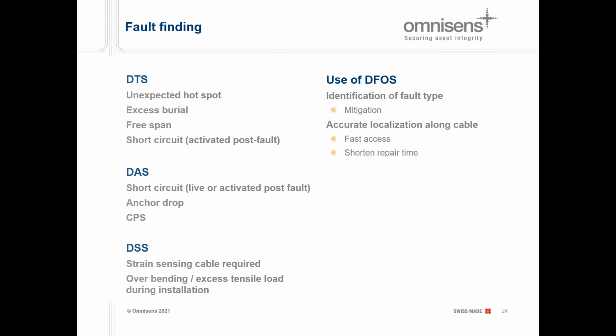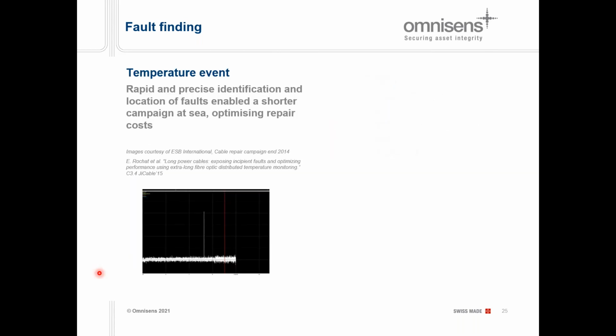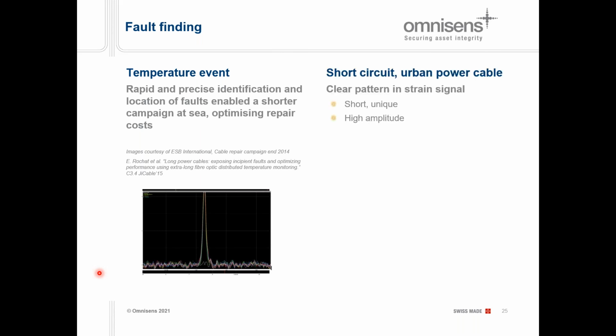A first example we published a couple of years ago relates to a fault found using DTS on a cable where the company had been looking for the fault for months. Eventually they decided to give DTS a go. Fortunately there was a fiber there, and when they activated the fault, there was a clear hotspot, easily localized. With fine-tuning and validation they could go to the spot and do the repair. Localization in this case took about a week, since they used a kind of habitat placed around the cable in the water to do the repair.